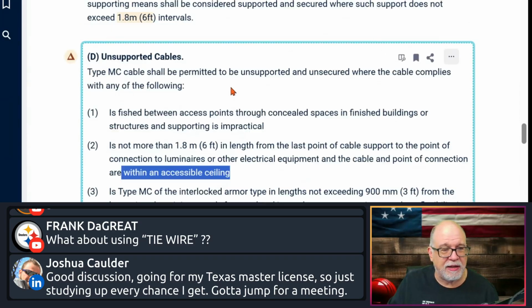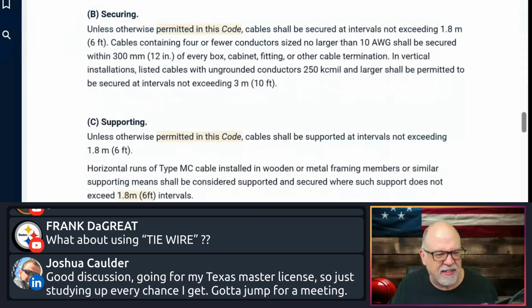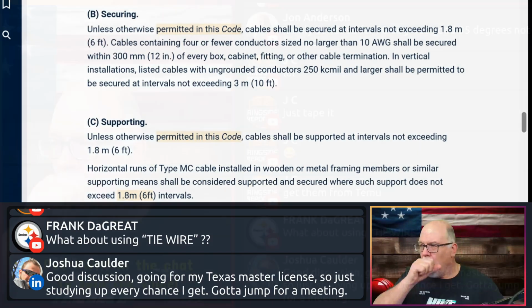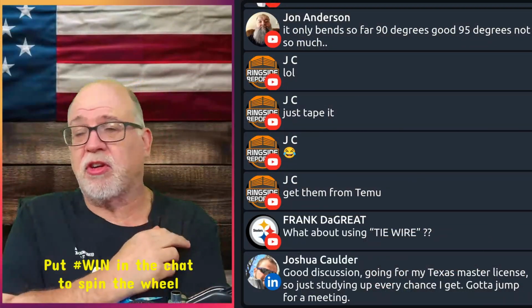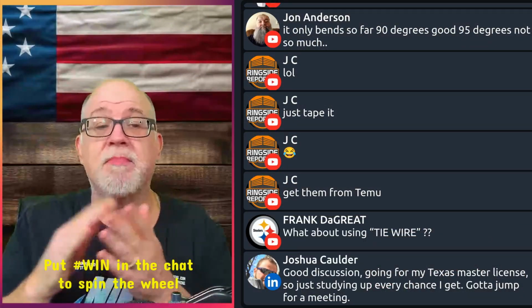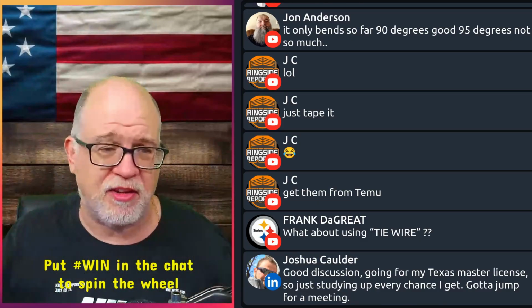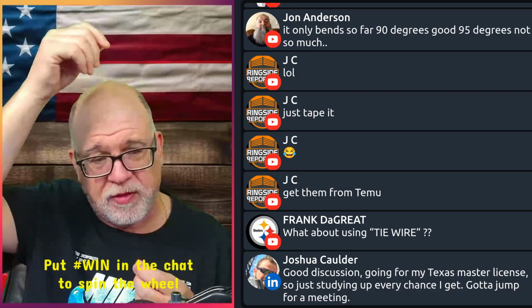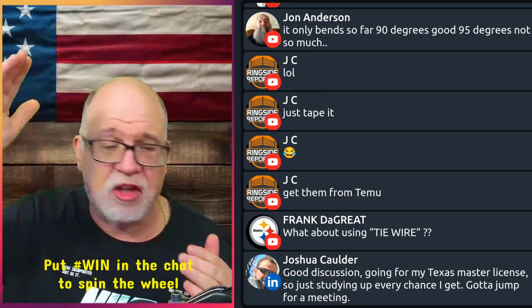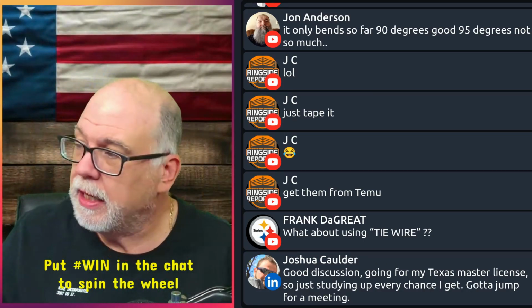Now, I believe that most AHJs will, this is a good example where I tell people all the time, what happens if I want to do this and I'm in a jurisdiction that doesn't make this as clear because they're on an earlier edition? What can I do? Well, one of the things that you can do is go to your jurisdiction and see if they will let you do an amendment, a modification. Maybe you have hundreds of these in the ceiling and they're making you put bat wings and run your own separate securement from the ceiling to the grid just for that MC, just a little 6 foot of MC. And you're like, Jeez, that's going to be a lot of work. And in the 2023 code, it makes it very clear, right?